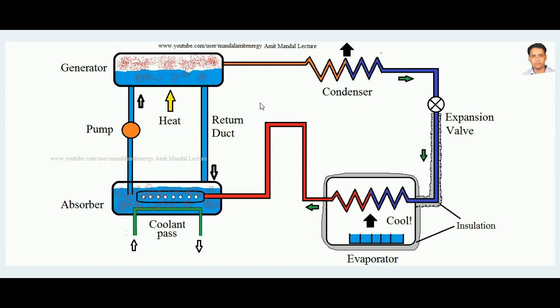This type of refrigeration system is used in industries where waste heat is available, because the compressor is replaced by heat alone to develop the refrigeration effect. For a solar refrigeration system, the absorber is kept in a cool area while the generator is kept in a sunny area. Direct sunlight or a concentrating arrangement focuses more sunlight onto the generator, liberating ammonia from the water.